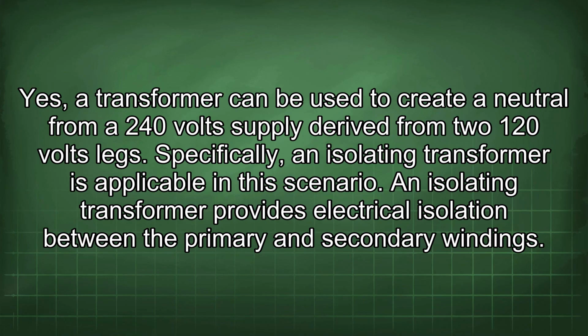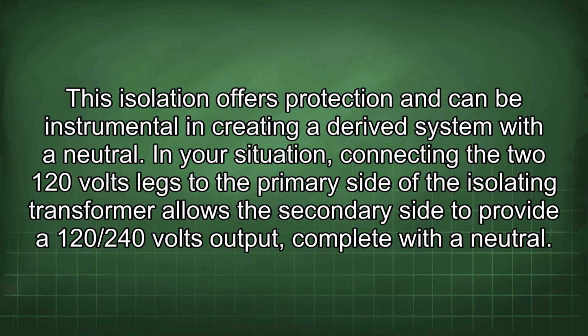Yes, a transformer can be used to create a neutral from a 240-volt supply derived from two 120-volt legs. Specifically, an isolating transformer is applicable in this scenario. An isolating transformer provides electrical isolation between the primary and secondary windings. This isolation offers protection and can be instrumental in creating a derived system with a neutral.